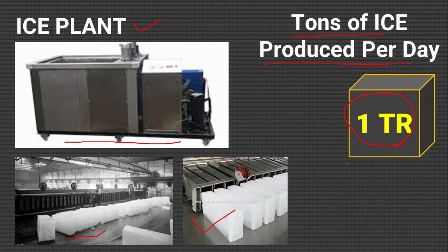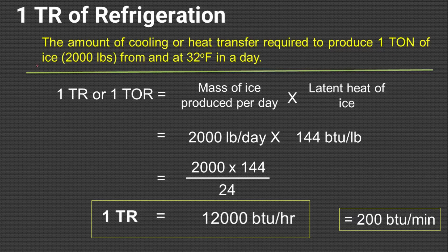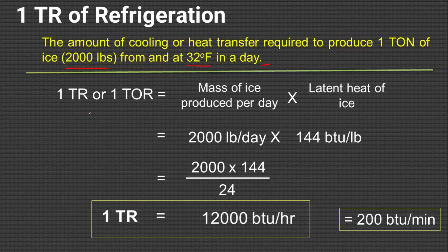Tons of refrigeration was introduced in the USA, and hence they defined it in terms of imperial units. One can define 1TR of refrigeration as the amount of cooling or heat transfer required to produce one short tonne of ice — which is 2,000 pounds, or precisely 907.2 kg — from and at 32 degrees Fahrenheit, or 0 degrees Celsius, in a day or in 24 hours. It is clearly a rate — a rate of cooling or rate of heat transfer. We quantify rate of heat transfer in terms of Watt or BTU per hour. BTU means British Thermal Unit. Let us calculate it.